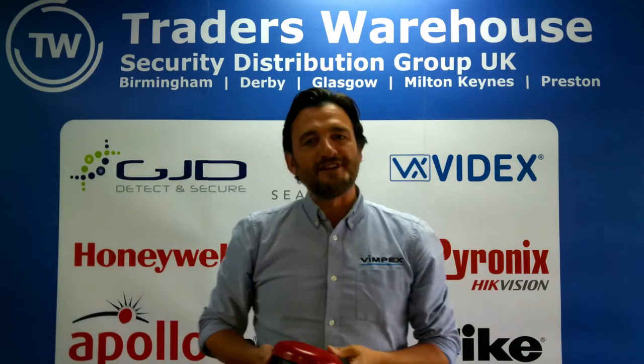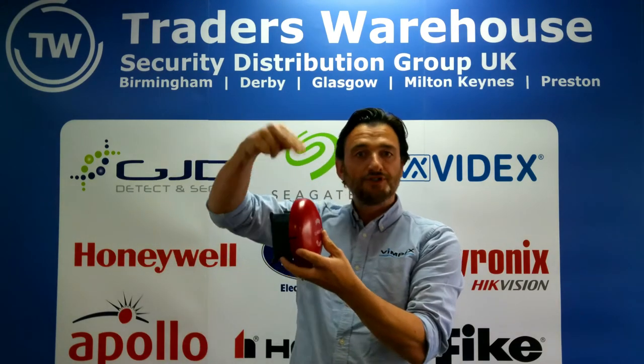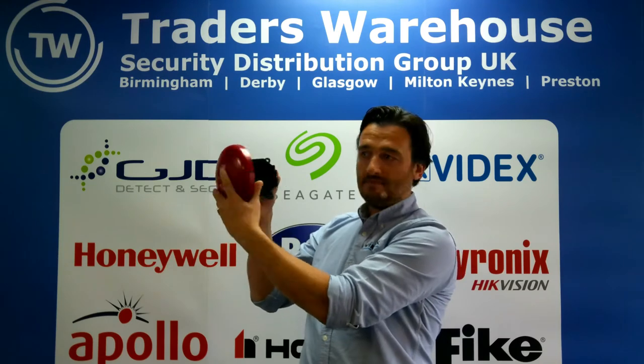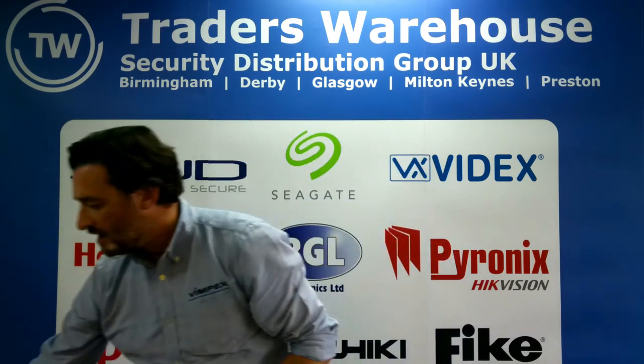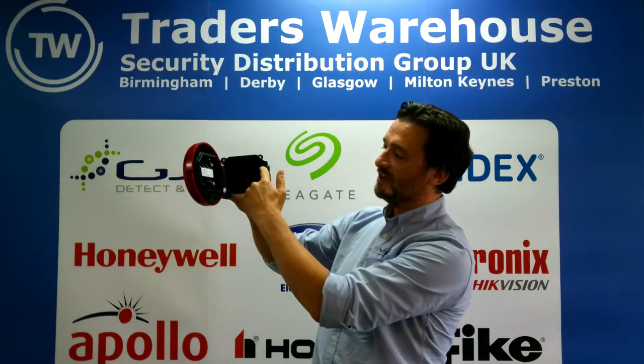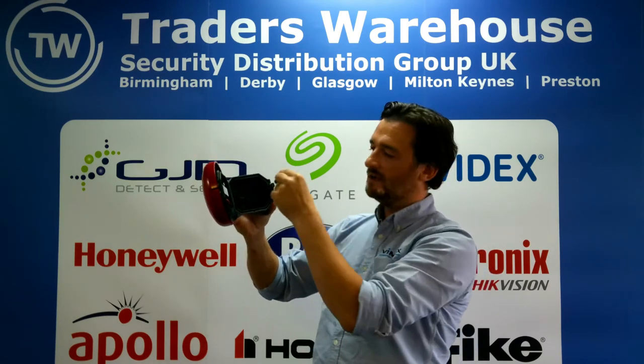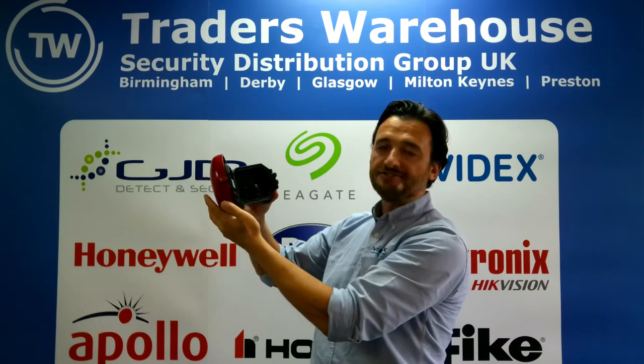The Clambell comes in three guises: flush mount for hidden wiring with a shallow base; surface mount on a deep base for surface wiring — again with the same Clambell clip function; and most importantly, a weatherproof version. This weatherproof enclosure actually features a robot-applied silicone seal and even comes with the correct glands for glanded entry.